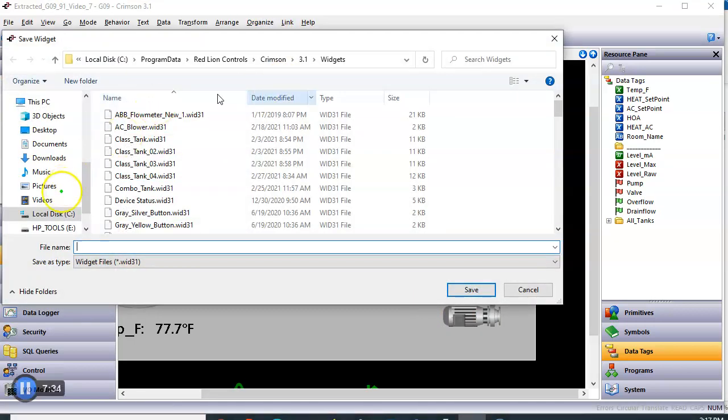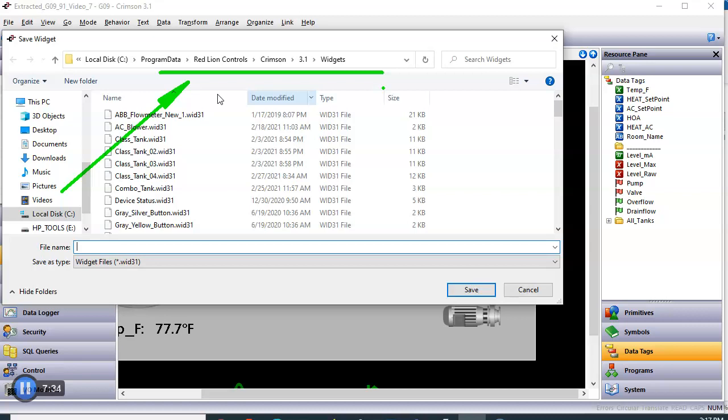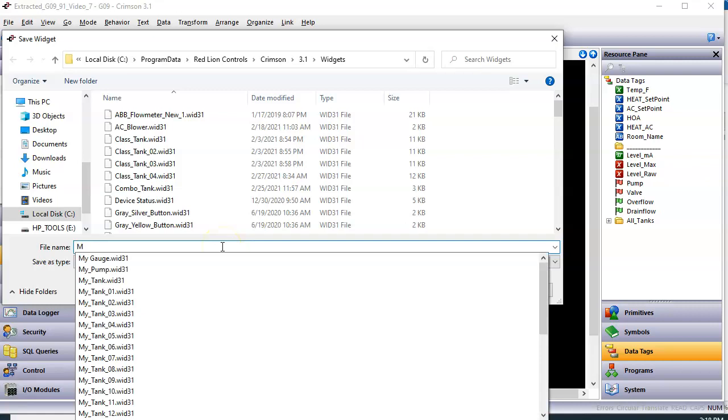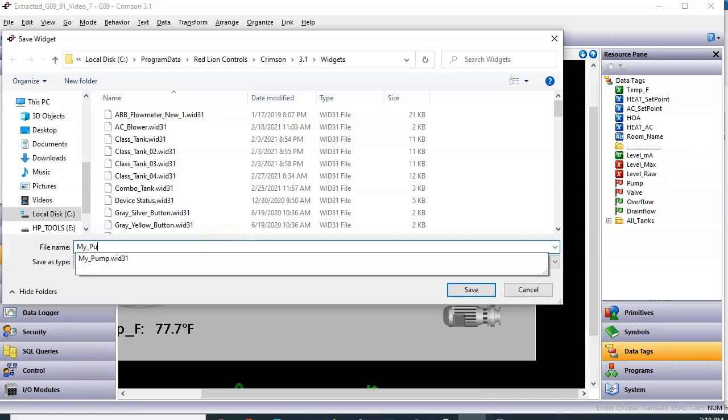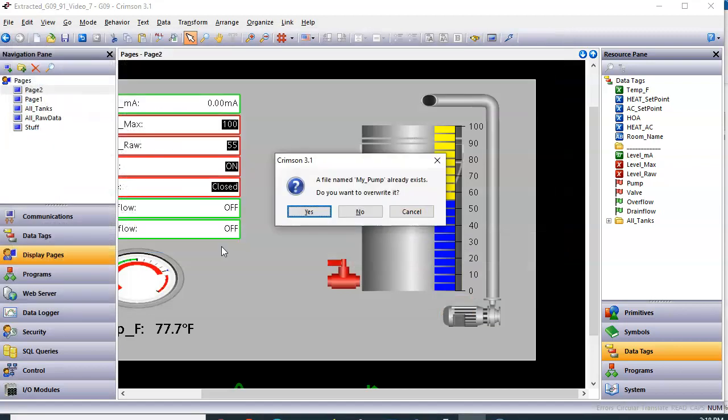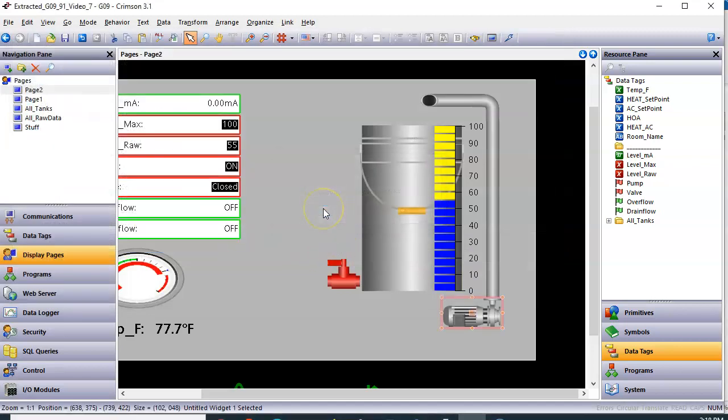Here's another caveat. You got to put it in this default directory. Yet today, we don't have a way to tell Crimson where to look at other directories for these widget files. So it has to go into this hidden directory. Don't put it somewhere else because Crimson right now is not going to see it. So let it go where it wants to. So down here, I'm going to type my pump. And I'll hit save. And I already had one, but I'll just go ahead and overwrite and save.